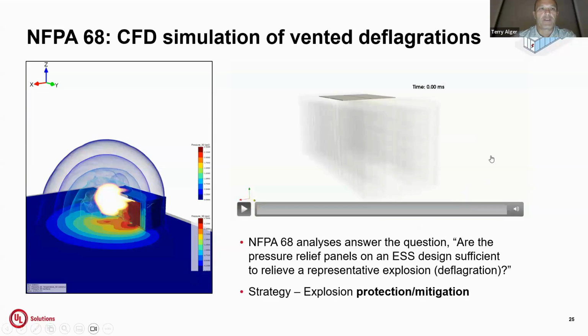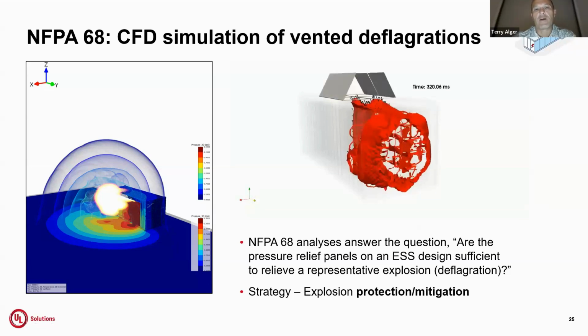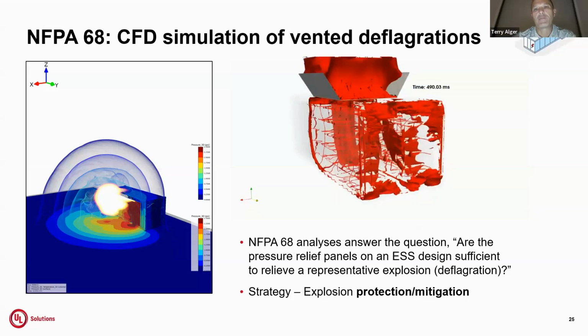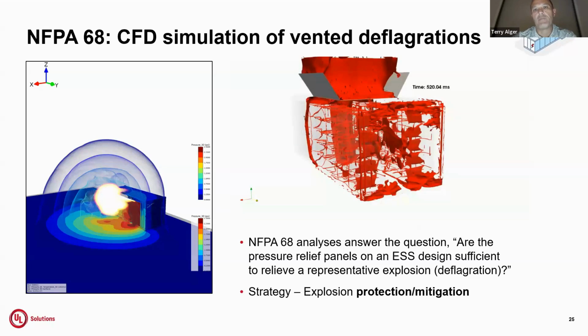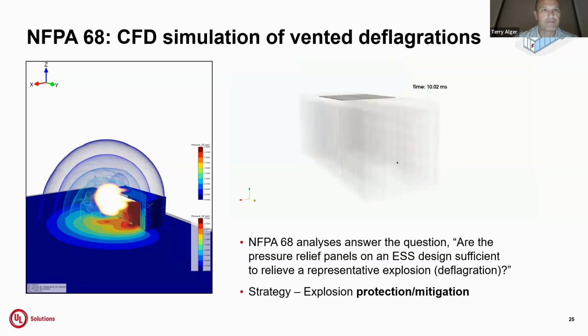NFPA 68 is a different case. Here, we assume that an explosion has occurred, and we're trying to determine if our explosion safety systems provide enough relief or panel surface area to prevent an overpressure event from damaging the structure and causing even more problems than the deflagration event itself.